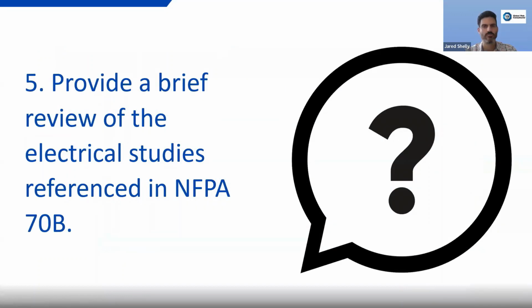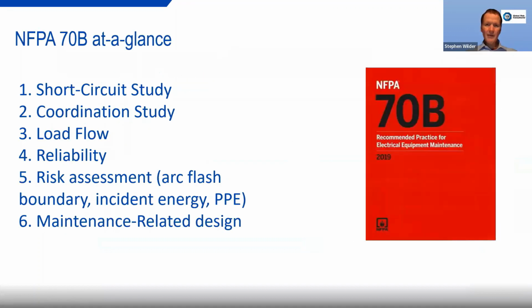And then, Stephen, can you provide a brief review of the recommended but not mandatory standards like NFPA 70B? Well, NFPA 70B recommends the best practices for electrical equipment maintenance. It provides, among other things, recommended scheduling to update the short circuit coordination and arc flash studies. These are not meant for personnel protection, but for protection of property. It's mostly maintenance related. It's not for personal protection.